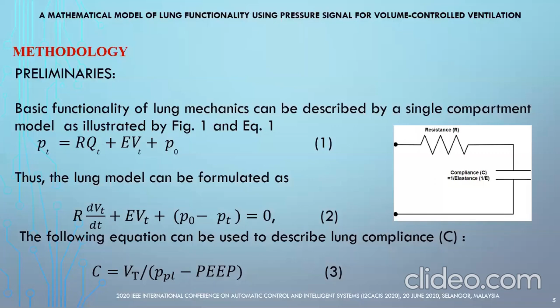The methodology is given by the figures from number 2 to number 4. Figure 2 provides the basic components involved in the proposed model. We can see in this figure 2, on the right part is the mechanical ventilator itself, and the flow is coming from the mechanical ventilator to the analyzer that gives us the measured data of the pressure signal, volume signal, and the airflow signal. And that flows through the lung, an artificial lung. Actually, that can be replaced by the actual patient lung, but we just want to test it, so therefore we just use an artificial lung here.